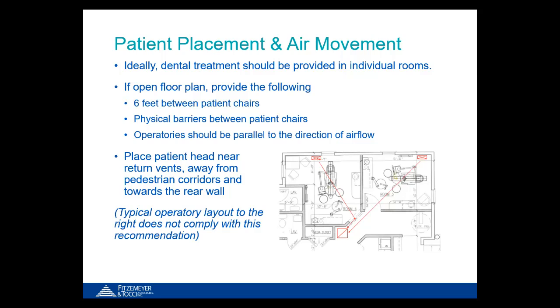In Dr. Keating's office, the supply grills are along the exterior wall, with a common return grill in the corridor just outside each room. With this layout, clean supply air comes out at the exterior, draws across the patient, and once it's contaminated from the patient's mouth, it's drawn right across the dentist's breathing zone before reaching the return grill. It's a bad design.